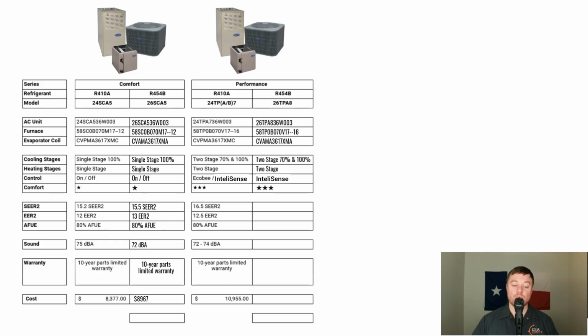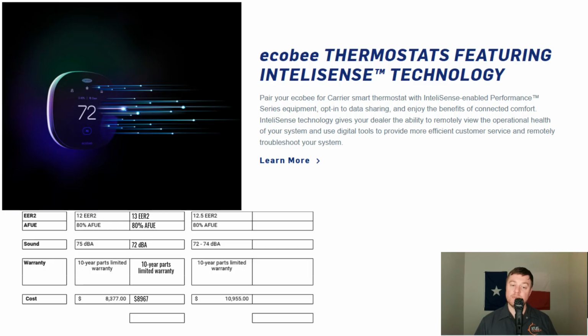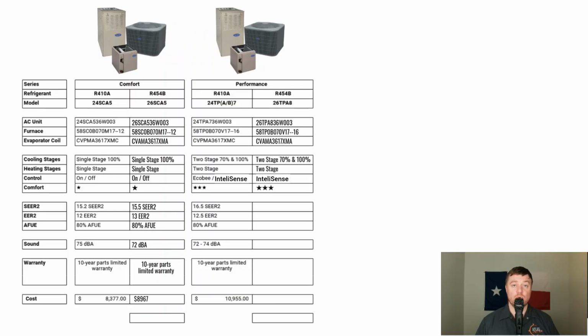Now when it comes to controls, there is a slight change here. If we look back up at the 410A model numbers, where we have a 24 TPA or 24 TPB, the A means the unit is an older model and does not come with InteliSense. The B means it's an updated model and does come with InteliSense. And for the new model, the 26 TPA, it only comes with InteliSense. Essentially, InteliSense does lightweight communicating for things like subcool and superheat and other error codes. And if it's connected to the cloud, it can report back to the contractor.